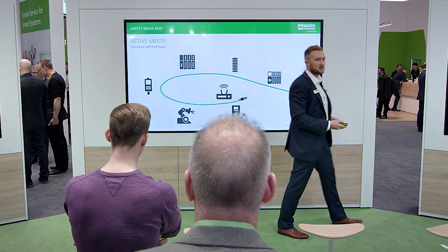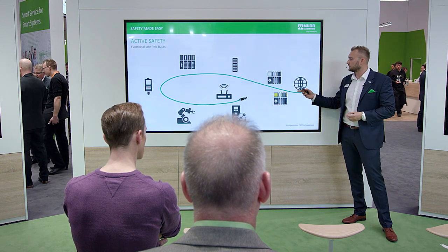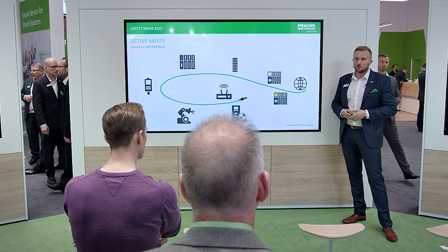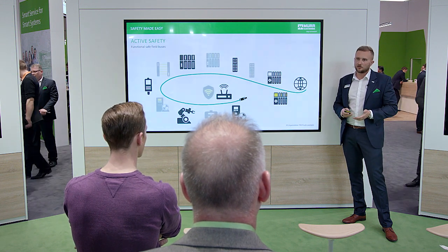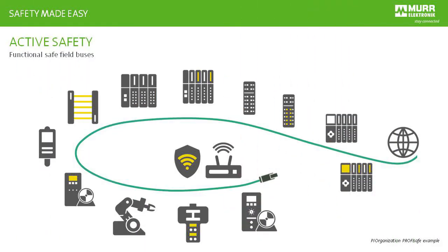If you consider now a safety PLC in your network, it doesn't have to be an additional one. You could exchange the standard one. You could use in the same network also the standard components. So both standard communication and safety communication in your already functioning network.